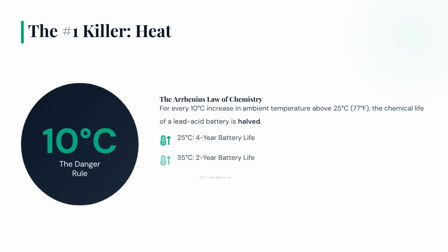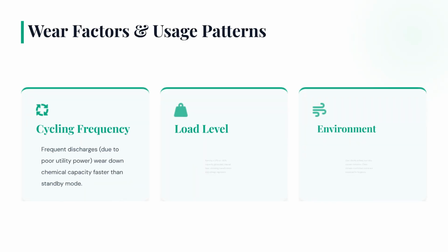The number one killer of UPS longevity is heat. The Arrhenius Law states that for every 10 degrees Celsius increase above 25 degrees Celsius, the chemical life of a lead-acid battery is halved. For example, 45 degrees Celsius cuts battery life to just 1 year. This illustration highlights how increasing temperature drastically reduces the expected lifespan of your UPS batteries, emphasizing the need for proper cooling. Usage patterns also impact wear.